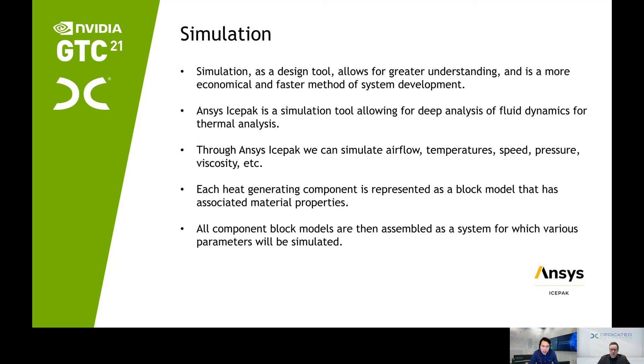Each heat generation component is represented as a block model that has associated material properties. We actually got the material properties of the CPU and GPU dice from Intel and NVIDIA. The material is called IHS — integrated heat spreader — including density, specific heat, conductivity, and radiation behavior. We also input the fan curve into IcePak, which is airflow versus pressure drop, and let the program determine the real fan operation points.